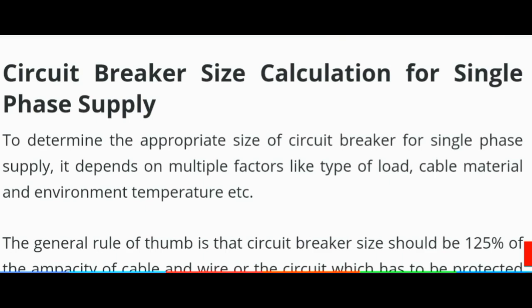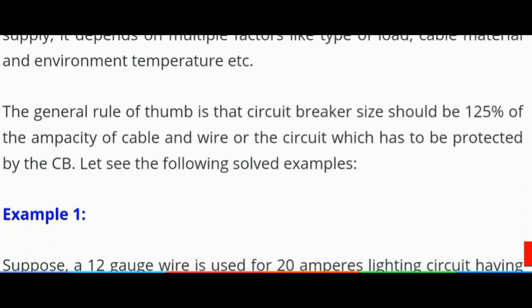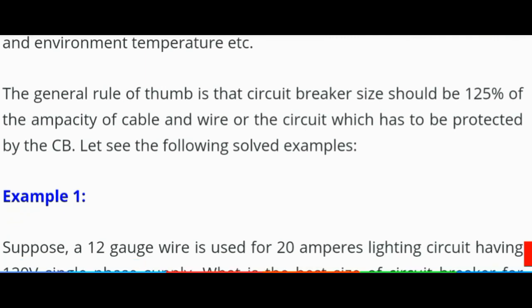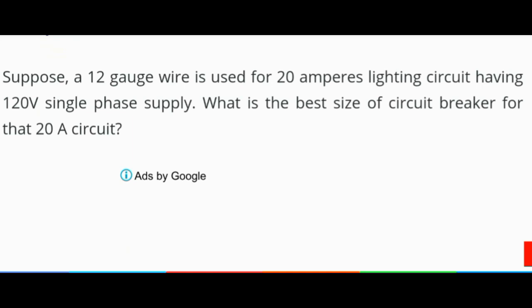The next topic is circuit breaker size calculation for single phase supply. To determine the appropriate size of circuit breaker for single phase supply, it depends on multiple factors like type of loads, cable material, and environment temperature. The general rule of thumb is that the circuit breaker size should be 125 percent of the capacity of the cable and wire of the circuit. Example 1: Suppose a 12 gauge wire is used for a 20 ampere lighting circuit having 120 volt single phase supply. What is the best size of circuit breaker for that 20 ampere circuit?